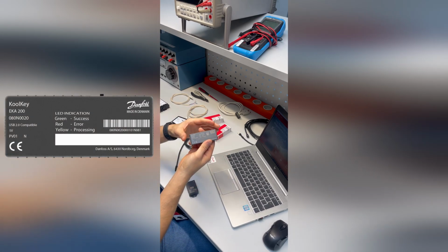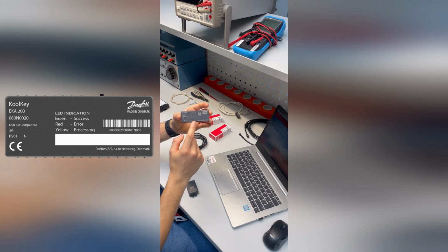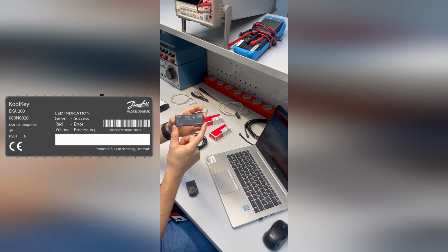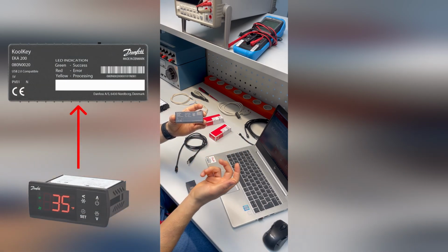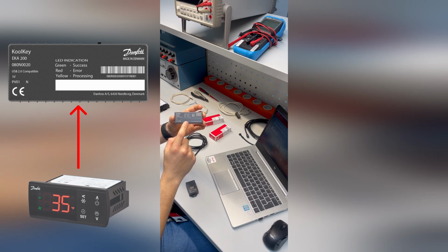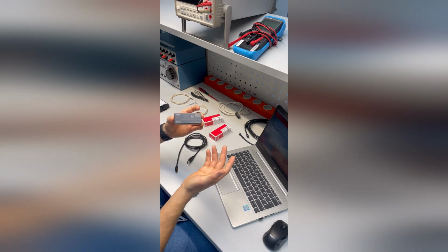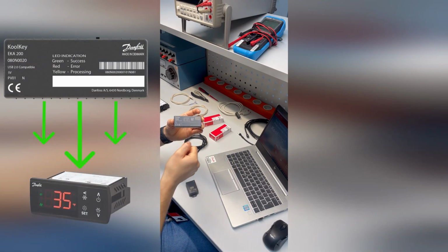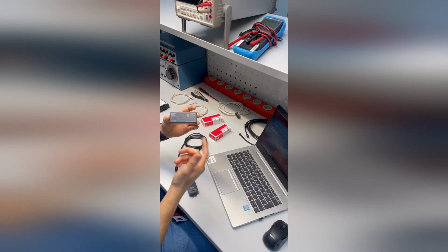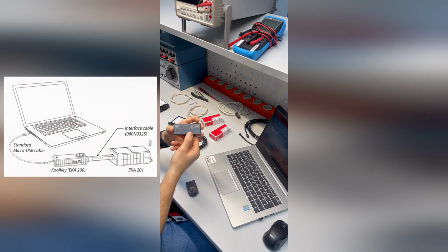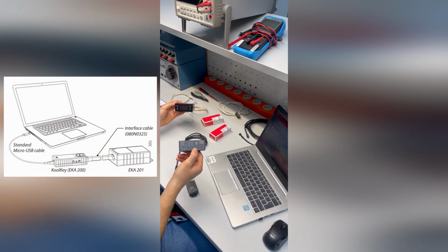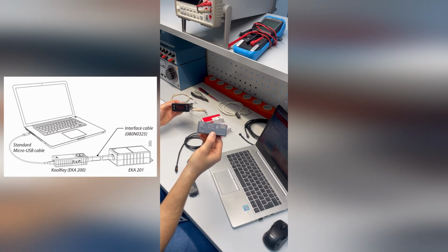The KoolKey has also the same feature as the MPK. It can be used as a mass programming key as well, but it has several other features. You can, for example, retrieve the information from your controller and store it here inside the KoolKey. You can have several different configuration files inside the KoolKey, and you can also use it, as I said, as a mass programming device. You can connect to your controller and download the configuration file inside the KoolKey. You can also use it as a gateway. It means that you can connect your ERC, for example, to your PC using the Koolprog via KoolKey.